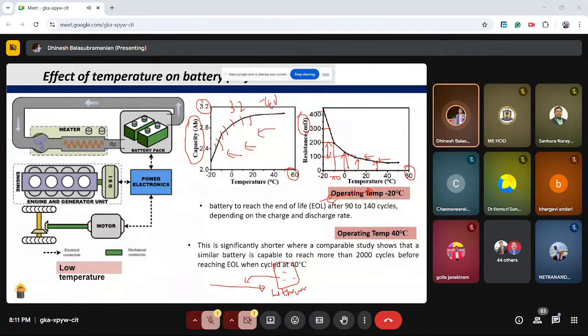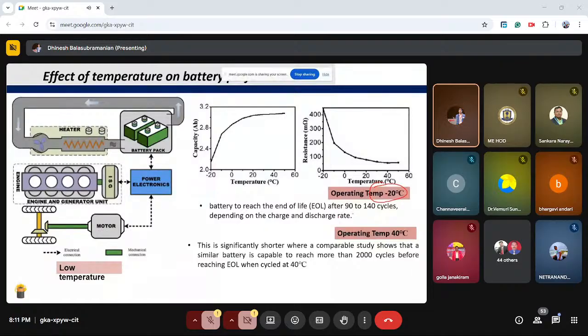And what would happen when you operate at two different temperature ranges, which I have mentioned here. When you look in detail, when you operate at -20 degrees Celsius versus a higher temperature of 15 to 35 or 40 degrees Celsius, there is a significant difference. A comparable study shows that a similar battery is capable of reaching close to 2000 cycles, and now it is 5000 to 7000 cycles for effective battery operation, before its end of life, which means the total cell capacity should not be less than 80% when cycled at 40 degrees Celsius. But when you operate the same system at -20 degrees Celsius, the end of life comes in just 90 to 140 cycles.